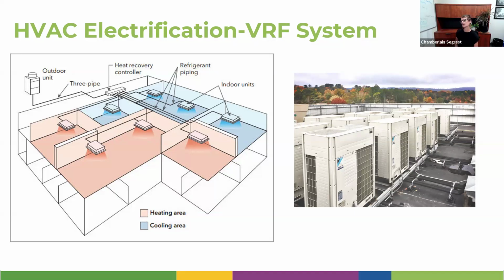The challenges of a VRF system: there's a lot of refrigerant involved, since it's pumped to each room to either heat or cool through a fan coil in the ceiling. That refrigerant is a greenhouse gas, and different refrigerants have different levels of global warming potential, so we're working with our design team to get on the lower end of that spectrum. But they can all leak, so that's something everyone needs to be aware of when installing these.